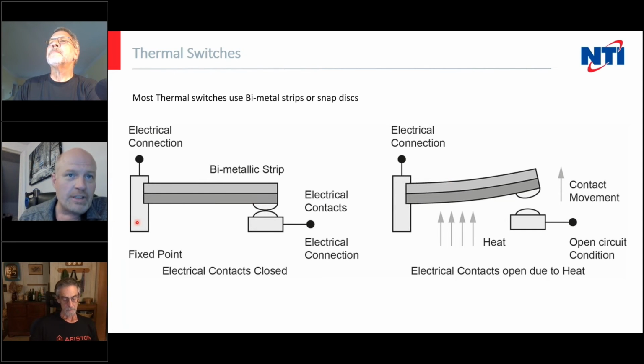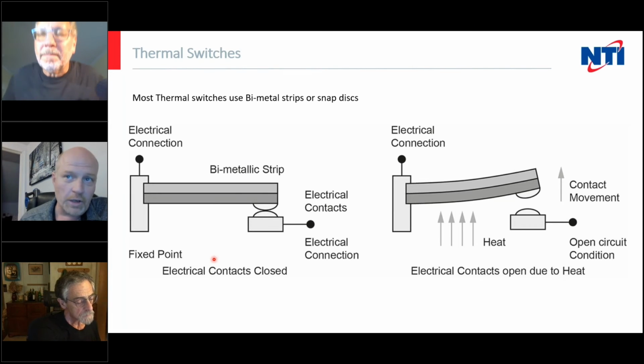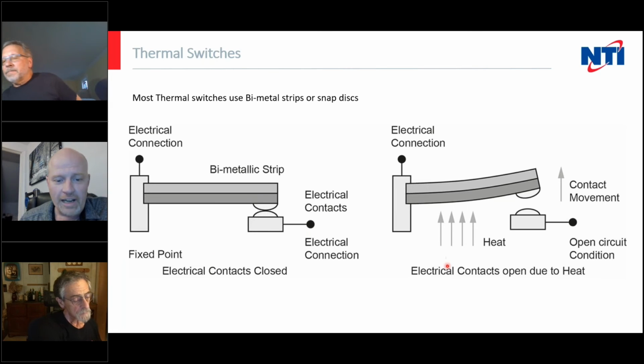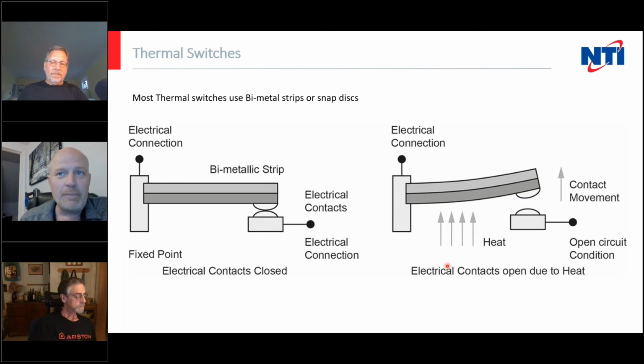Mostly these are resettable and they're either automatic or manual. If it's a snap disc, it's probably a manual reset, meaning you have to manually pop it back to make it work again. Most of the rest of them that don't have a button or anything are automatic reset, which means that as soon as they get cold enough, they start working again. And if you go buy a really cheap electric baseboard thermostat, this is how they work. It's a calibrated bimetallic strip. I've got a couple of Honeywell ones in my house.